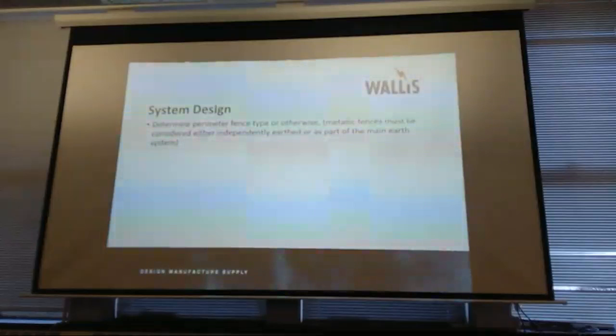Under fault conditions, if that fence is bonded to your HV earth, that fence is going to be at the same potential as the substation under fault. So you can have people walking up, grabbing the fence. The best way around that is to put a perimeter tape 1 metre off the fence line to equipotentialise the general mass of earth to the fence. But that's not always possible on a small site, so again, you've got to start looking at these things slightly differently.